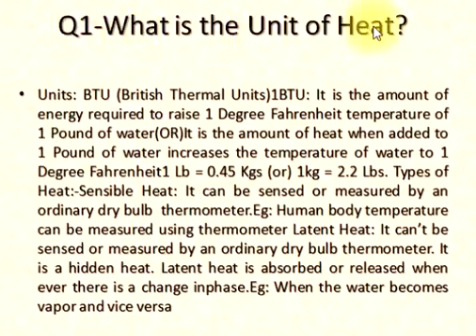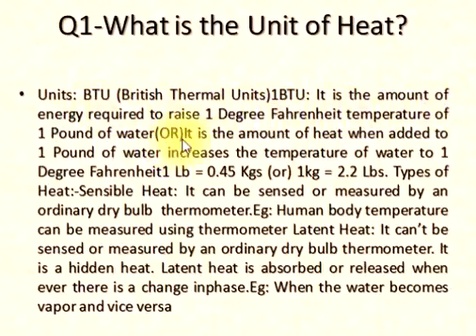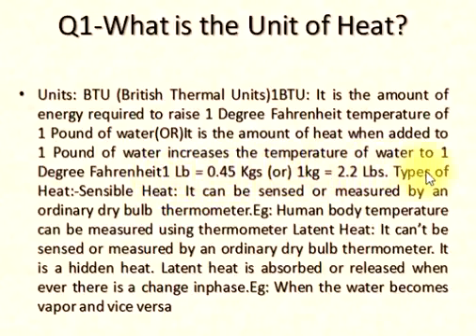Q1: What is the unit of heat? The unit is BTU — British Thermal Units. 1 BTU is the amount of energy required to raise 1 degree Fahrenheit temperature of 1 pound of water. 1 LB equals 0.45 KGS, or 1 kilogram equals 2.2 pounds. Types of heat: Sensible heat — it can be sensed or measured by an ordinary dry bulb thermometer.